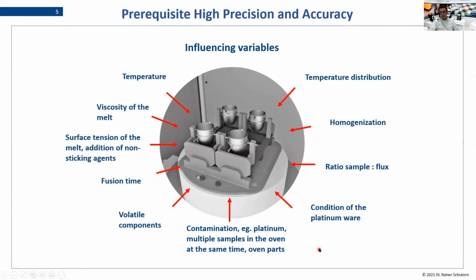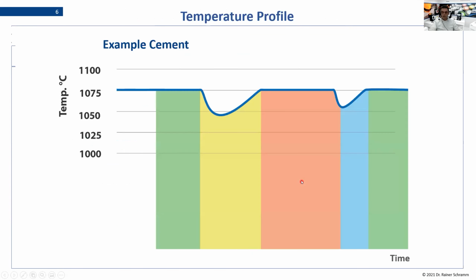Last but not least, there could be some contamination, either from the platinum ware or, of course, from the furnace system. That means things falling down from the ceiling, or cross-contamination from one sample to the next, or any kind of dirt which was collected in the furnace. These are all the parameters which influence our system, and only if we have them under control can we get a highly precise, highly accurate X-ray fluorescence analysis.